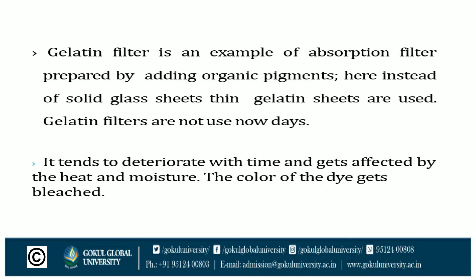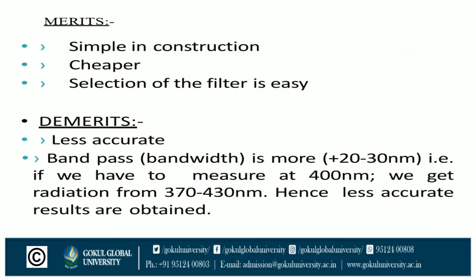Gelatin filters are not used nowadays. The merits of this type of filter are simple construction and cheaper, easier selection. The demerit is less accuracy because the band pass is wide — plus or minus 20 to 30 nanometers. For example, measuring at 400 nanometers gives radiation from 370 to 430 nanometers, resulting in less accurate results.